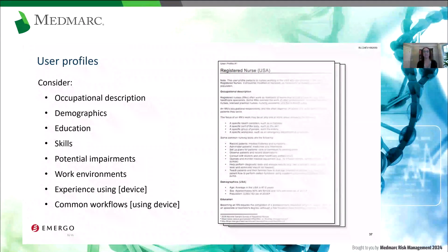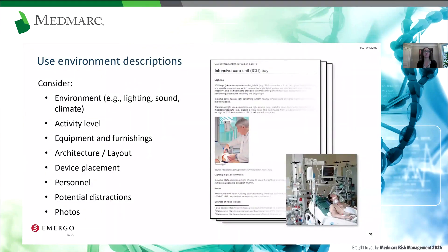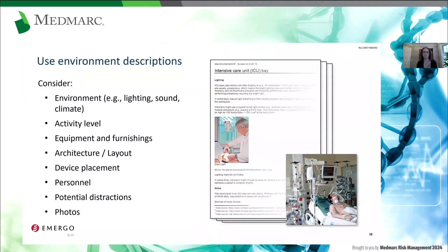These user profiles serve as a nice reference in the library of sorts for the human factors team and development team as they proceed with development. This is where you would capture things like: do users have any potential impairments — visual, dexterity, or cognitive — that you need to know about to ensure your design accommodates their safe and effective use? We take the same approach for use environments, describing them in terms of lighting, sound, distractions, what other equipment might be in the room, what other people are present, and we often try to instantiate this with photos. There may already be this type of content somewhere in your design history files, from marketing or clinical or past work, that can serve as a really nice starting point.